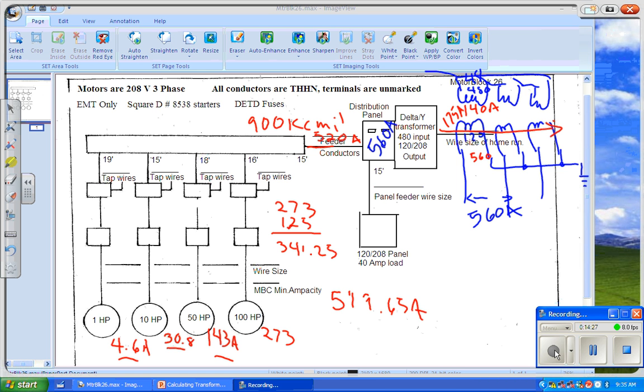All right. Is there a 202 kVA transformer? No, there's 175 and there's 225. And you have to know what sizes you can look up that you can use. So this is going to step us up to a 225 kVA transformer. And I believe that's the size, but I'm not dead positive. Now, have I left anything else out on transformer size? So we know this would be about at least 202 kVA, right? And we know that we would have 175 amp wires coming to it, and we would have 900 kcmil wires going to the auxiliary gutter from the transformer distribution panel. Not the main distribution panel, but the transformer distribution panel. Okay, let's stop there.